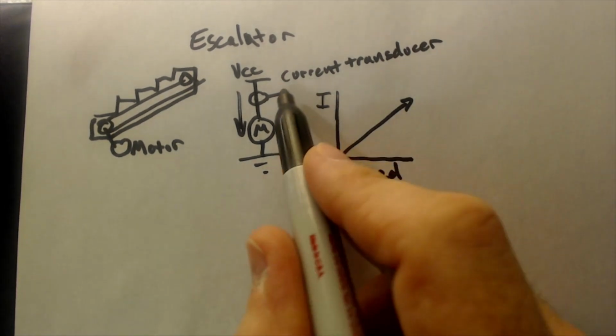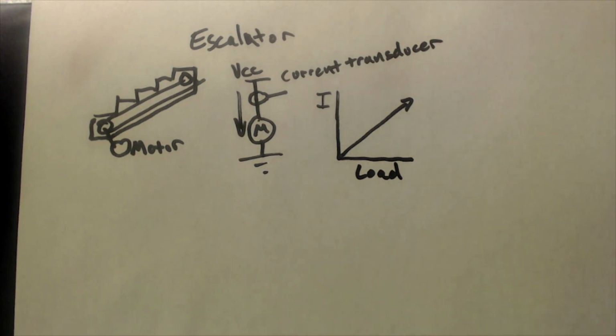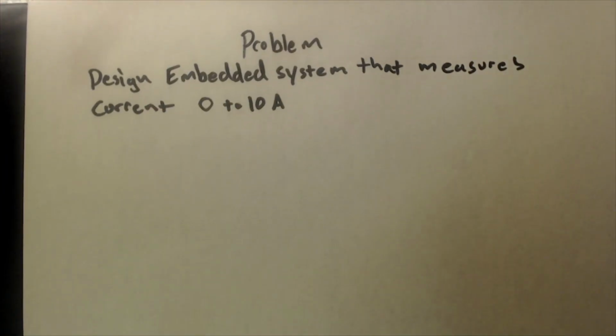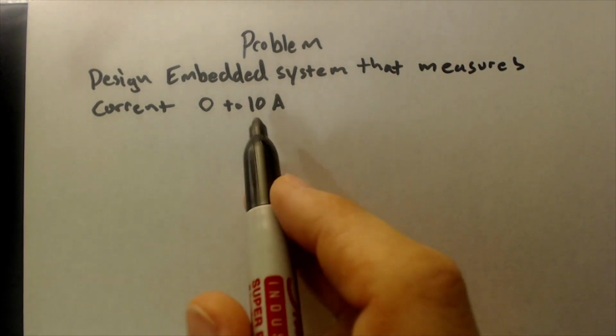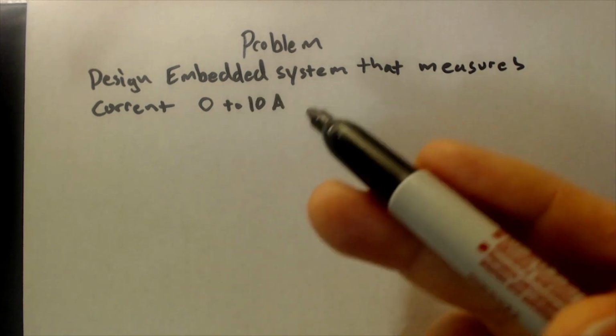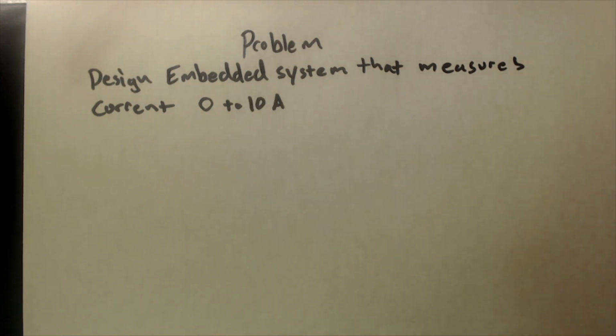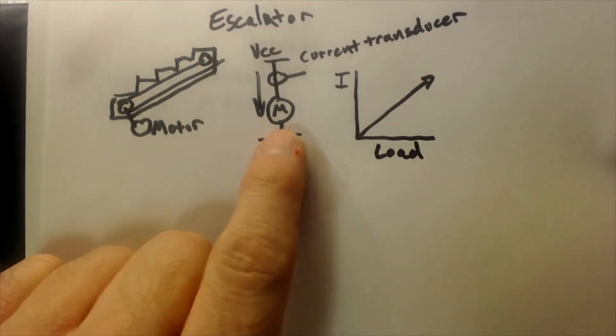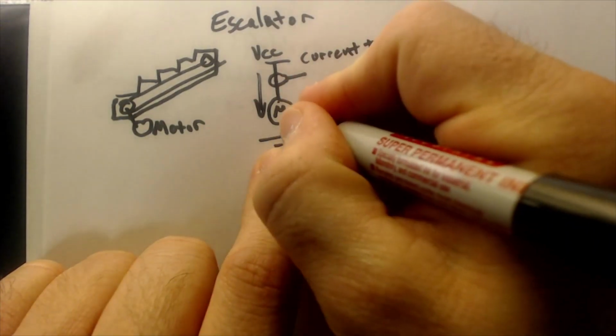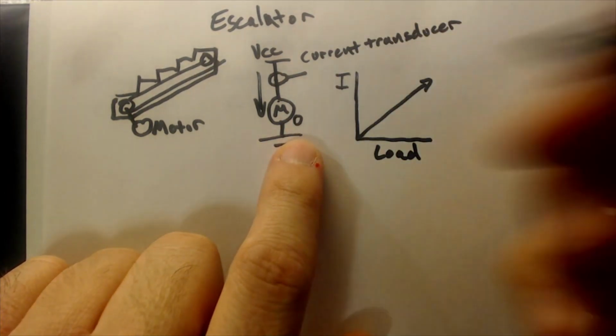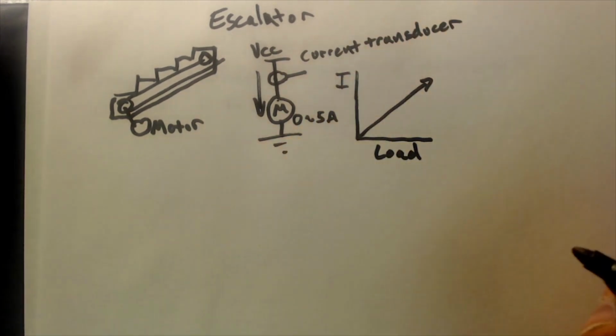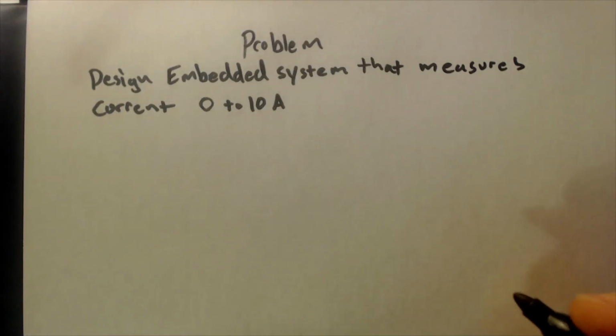So we need a current sensor, and we go out to purchase one. As it turns out, we can't find a current sensor that measures from 0 to 10 amps. Let's say 10 amps is small for an escalator motor, but bear with the analogy. Normal operation is 0 to 5 amps, so we want a current measurement that does 0 to 10 amps, so that when it goes above 5 amps, we can trip a fail-safe and turn the motor off.